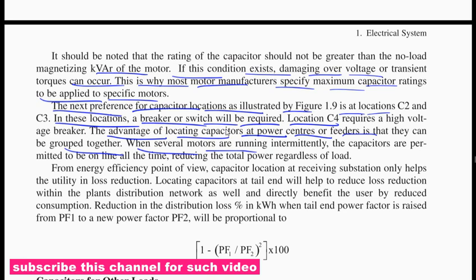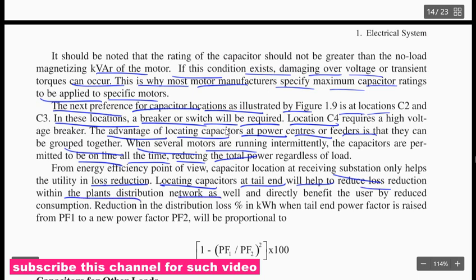The capacitor is permitted to be online all the time, reducing the total power regardless of load. From the energy efficiency point of view, capacitor location at the receiving substation only helps the utility loss reduction.